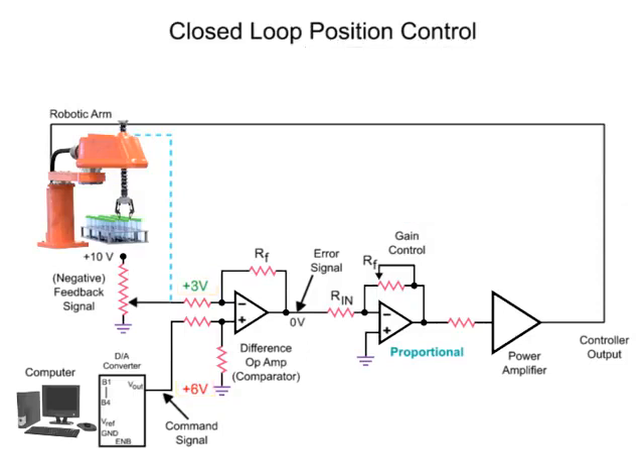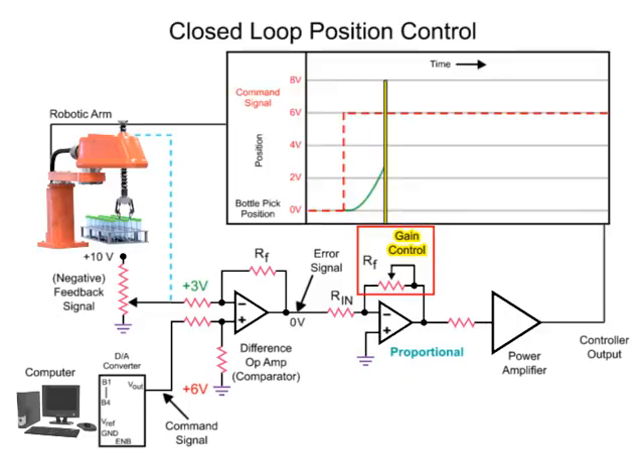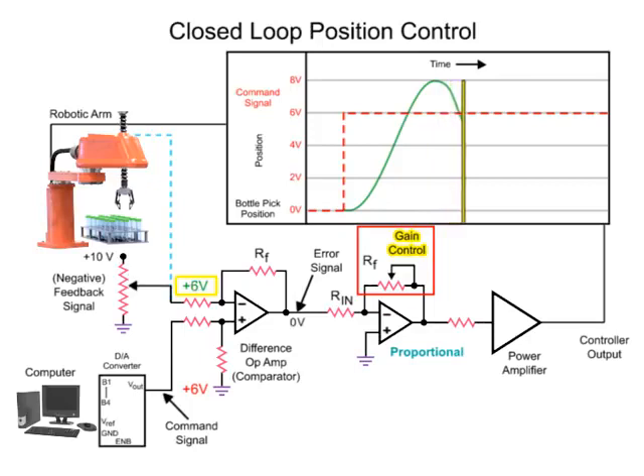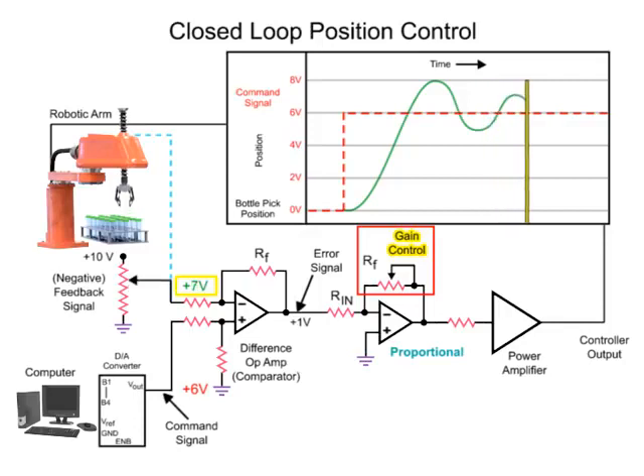To increase the response time of the robotic arm to the command signal, the gain of the proportional amplifier can be increased. However, increasing the gain has a disadvantage where the robotic arm overshoots the targeted position. When this occurs, the feedback signal is greater than the command signal, and the op-amp reacts by changing polarity from positive to negative, resulting in reverse rotation of the arm motor. Although with high gain, the overshoot is repeated again in the opposite direction, and this repeats until the robotic arm motor stabilizes.